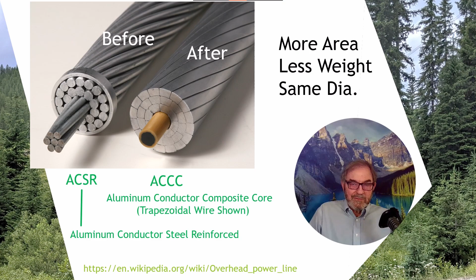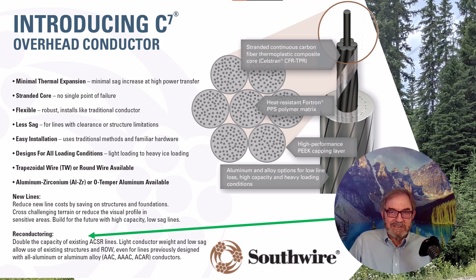The existing ACSR from the early 1980s is on the left, and the ACCC composite core trapezoidal conductor on the right. We get 33% more conductor cross-section per conductor by eliminating the air spaces and reducing the core diameter. 4 of the composite core conductors will have twice the cross-section area of 3 of the steel core and weigh little more. The green arrow points to reconductoring to double the capacity of existing ACSR line, which also doubles HVDC conversion capacity.